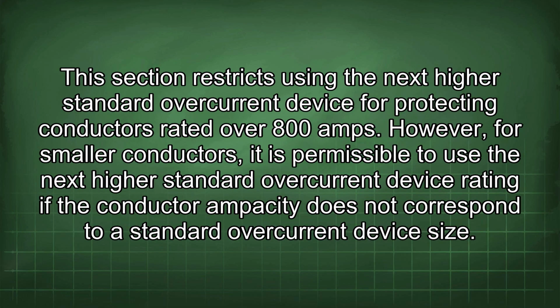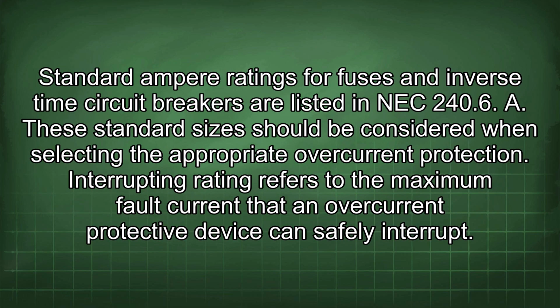This section restricts using the next higher standard overcurrent device for protecting conductors rated over 800 amps. However, for smaller conductors, it is permissible to use the next higher standard overcurrent device rating if the conductor ampacity does not correspond to a standard overcurrent device size. Standard ampere ratings for fuses and inverse time circuit breakers are listed in NEC 240.6. These standard sizes should be considered when selecting the appropriate overcurrent protection.